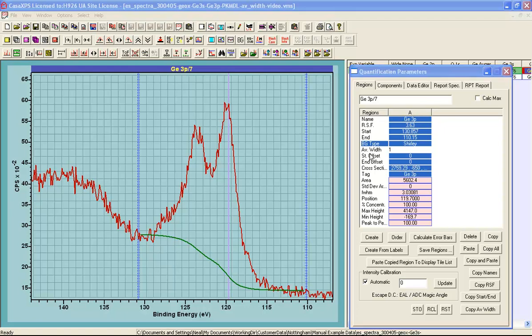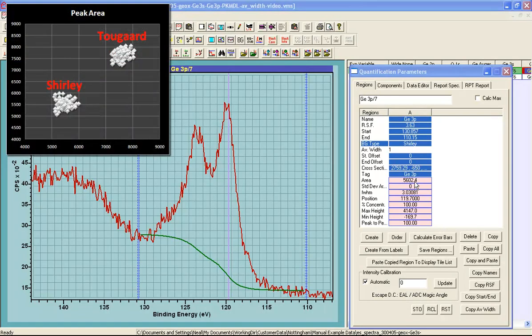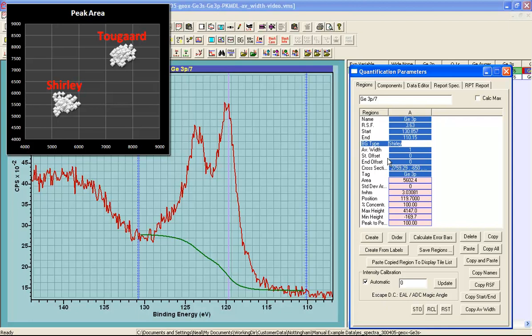The two parameters within this region that I have highlighted, the background type and the average width, behave differently in terms of calculating a peak area. The background type alters the area of the peak. So this represents a parameter that changes the accuracy with which we measure a peak.